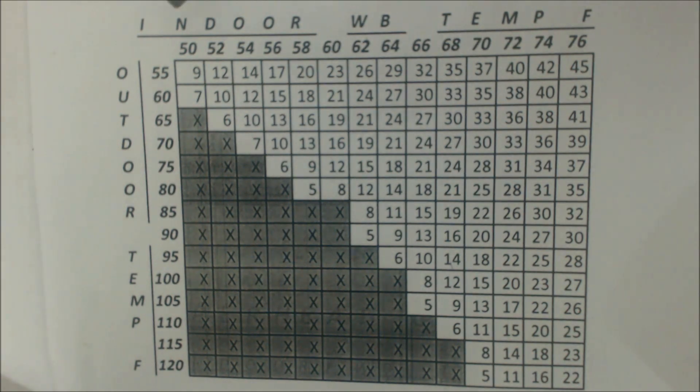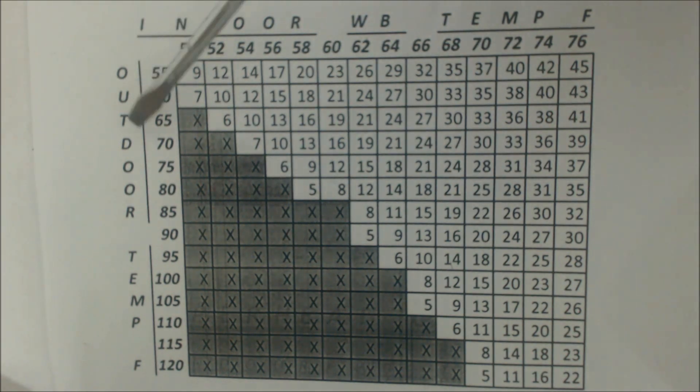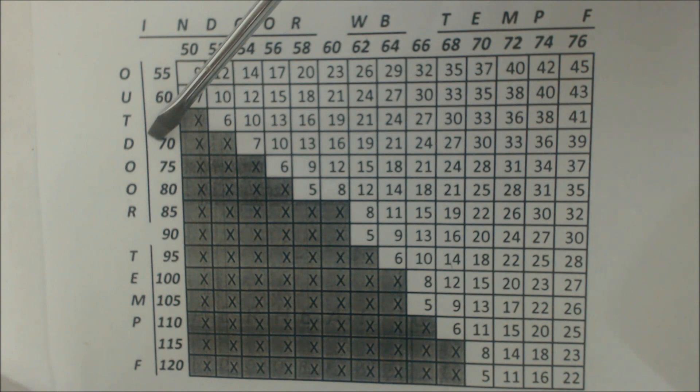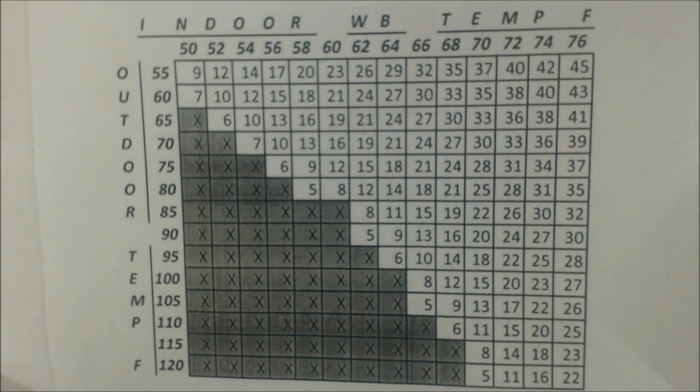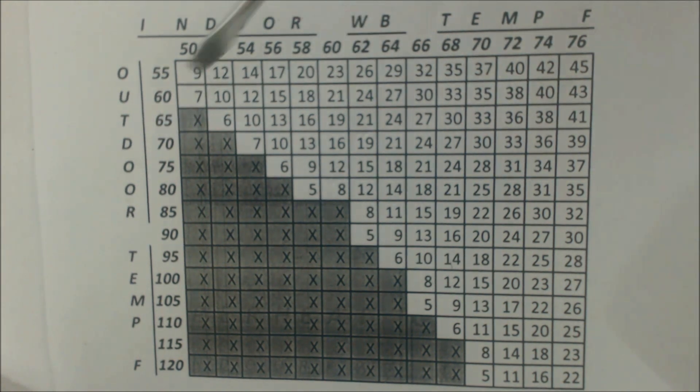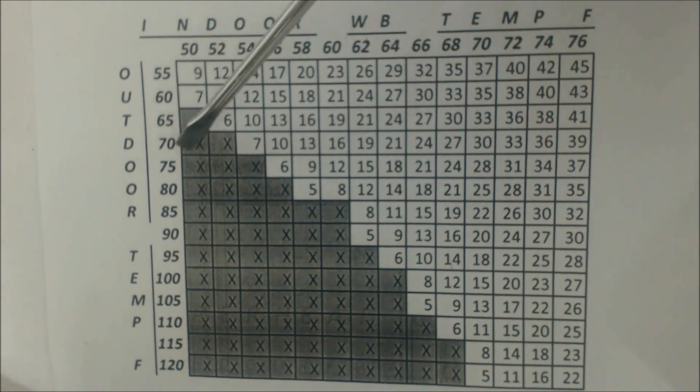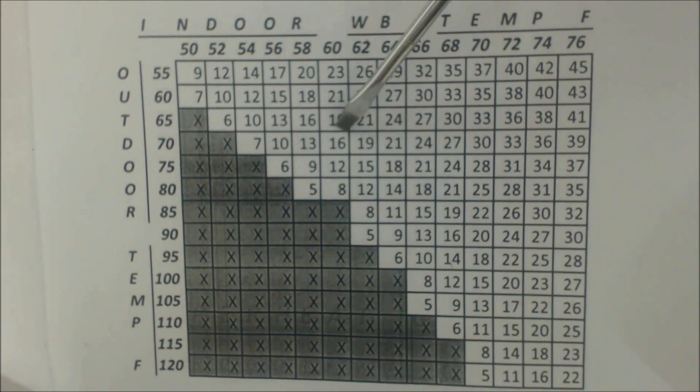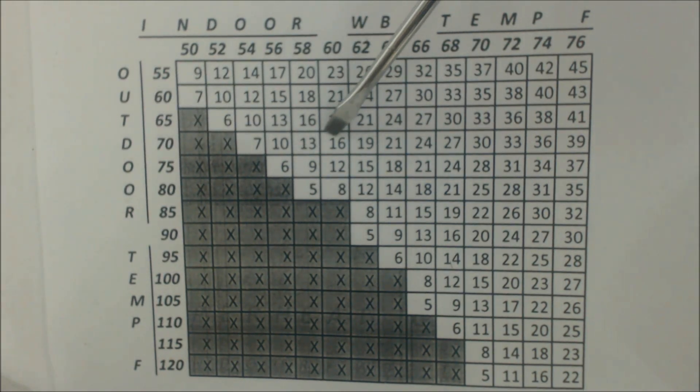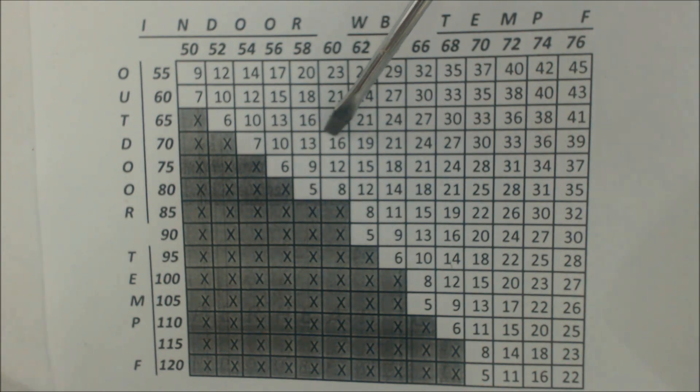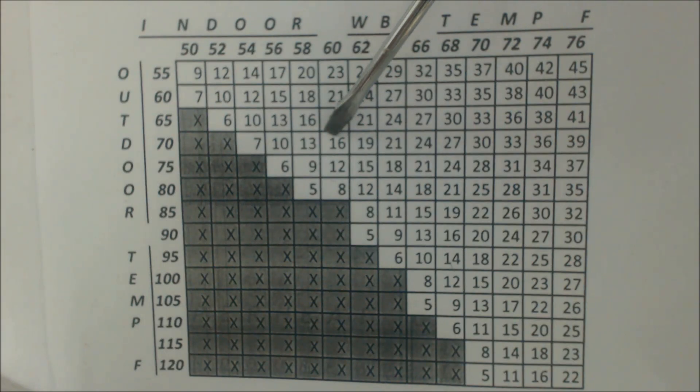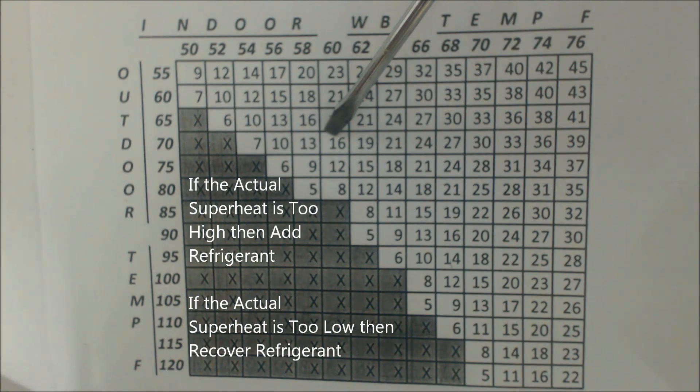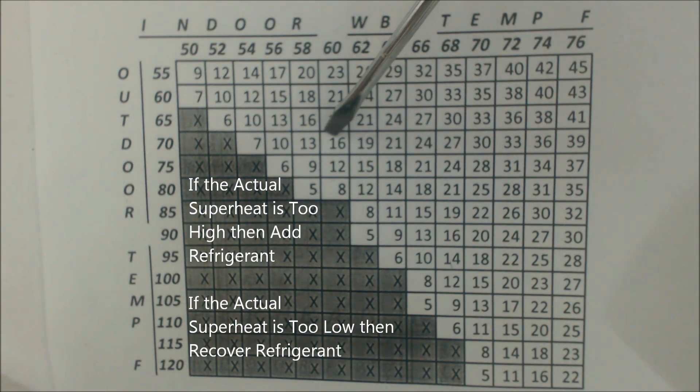Let's just say our outdoor temp is 70 degrees and our indoor wet bulb temp is 60 degrees. We line that right up, follow that over, and we find that the target superheat for the system on the large suction line with the blue gauge is 16 degrees of superheat. So temperature increase in vapor form. If our actual superheat was say seven, that would mean there's too much refrigerant in the system and you would need to recover that refrigerant.